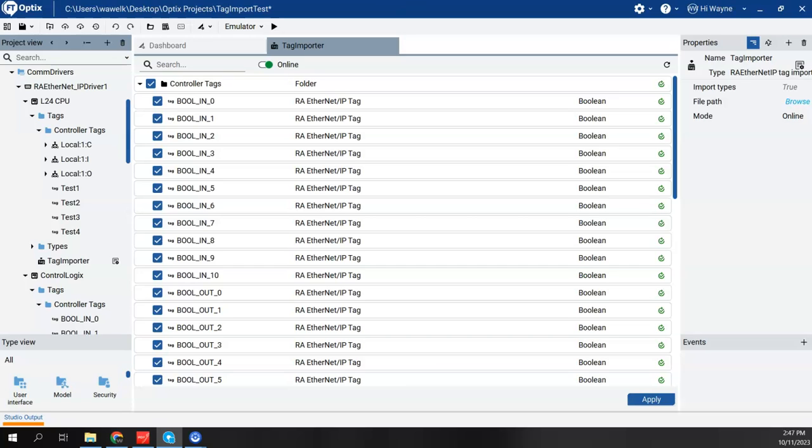Also, if you're trying to bridge through an Ethernet module and a Control Logix chassis, the ENET, the ENBT, and the E-Web modules, which are all older Control Logix Ethernet modules, are not supported. So we're going to use our newer Ethernet modules, such as the EN2T, the EN2TR, or the EN4T, the EN4TR. Those will be supported for Optix.